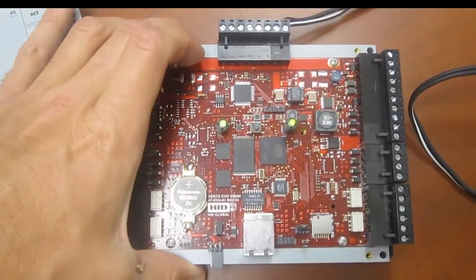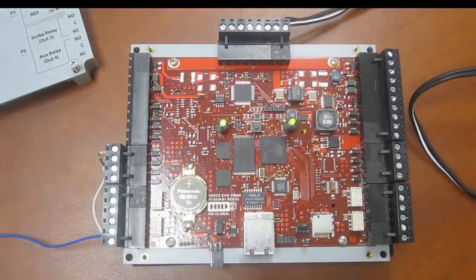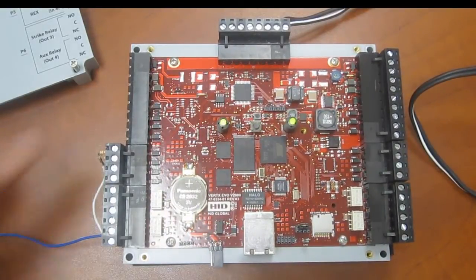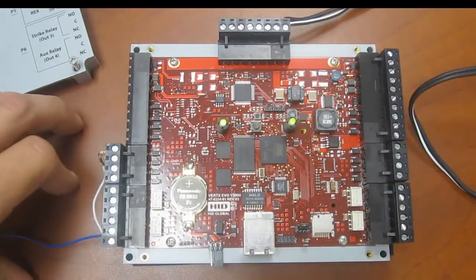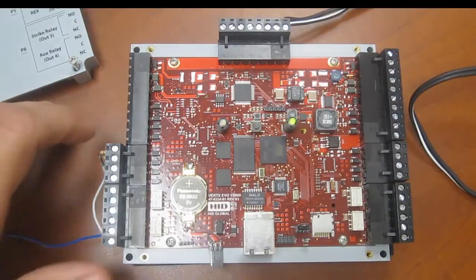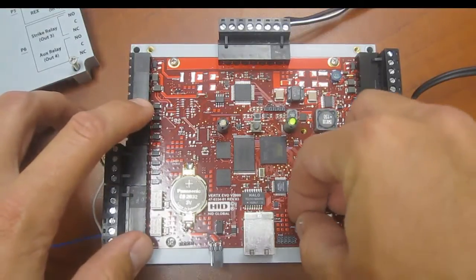Once the jumper has been put in place, we'll want to wait for the end of the reset cycle and the LEDs indicating that the reset was successful. 5 green flashes indicates that the reset was successful. 5 red flashes indicates that the reset was unsuccessful. If unsuccessful, power down the device, power back up, and repeat the sequence.